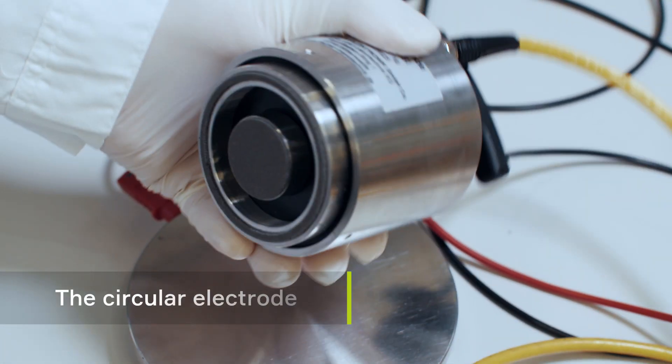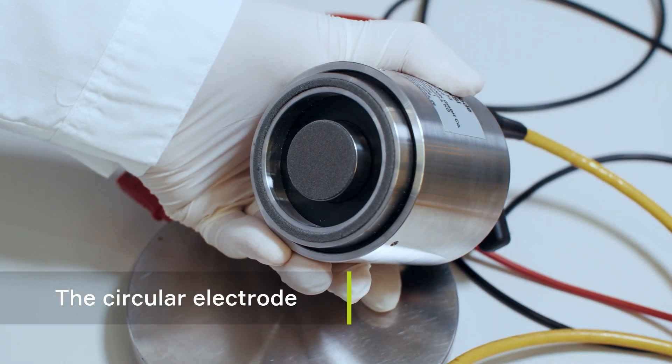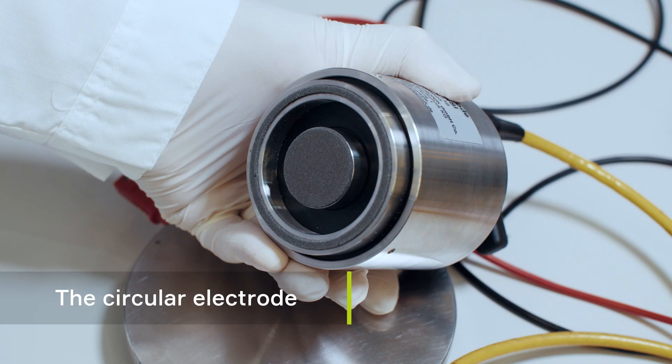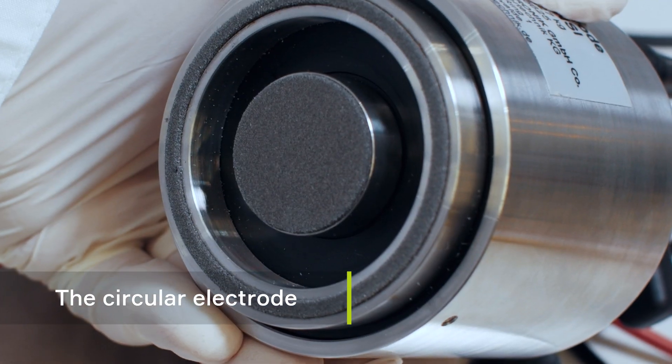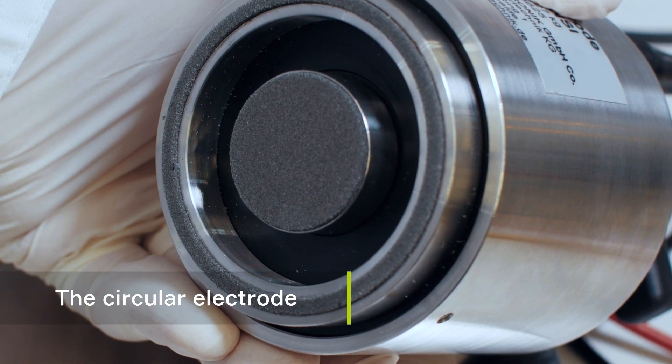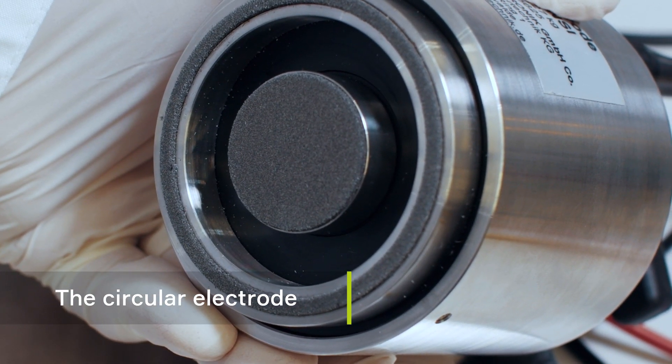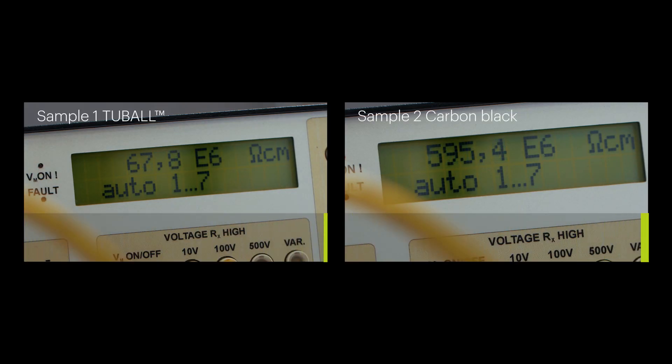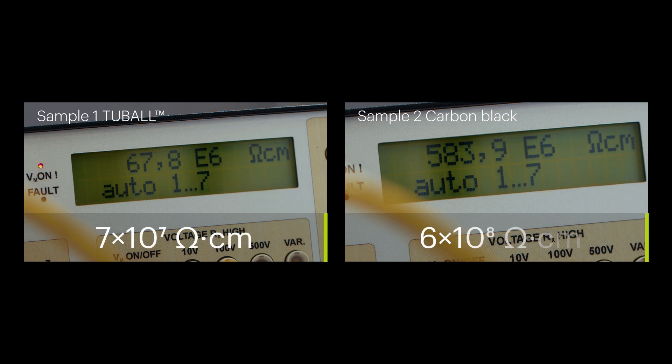The typical type of electrode, the circular electrode, is a round electrode inside a ring, as indicated in the standard. This electrode configuration confines the measurement of surface resistance to the area between the circular and ring electrodes.